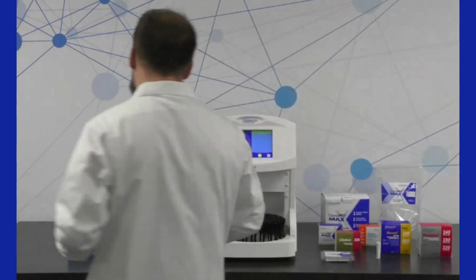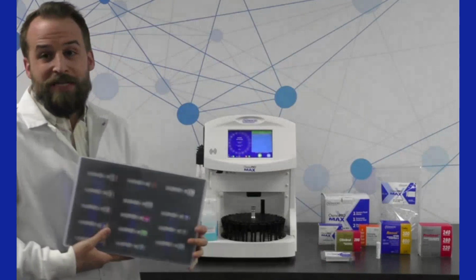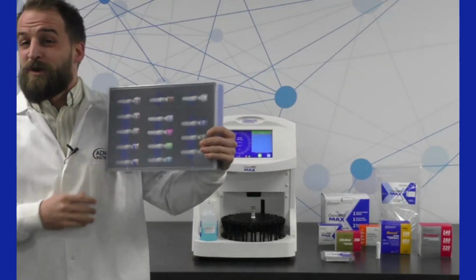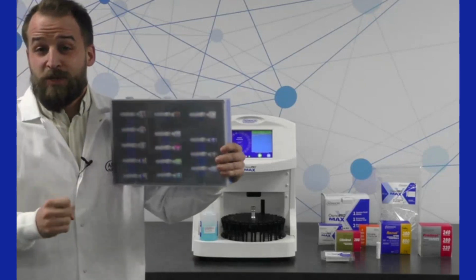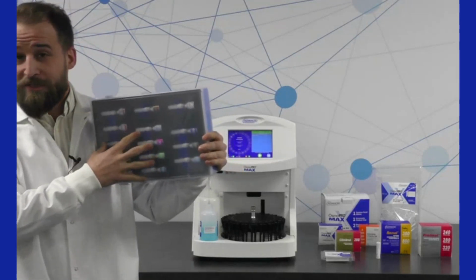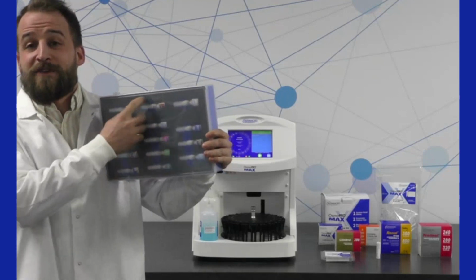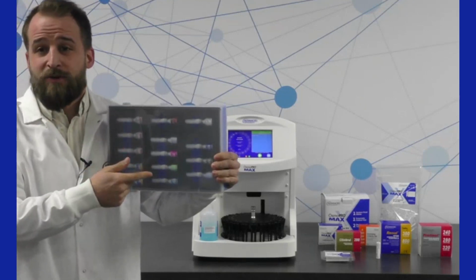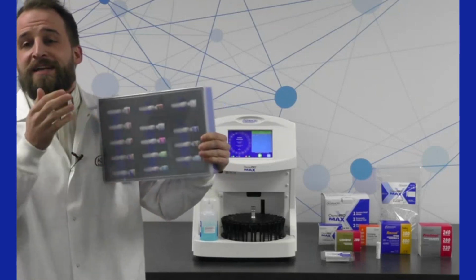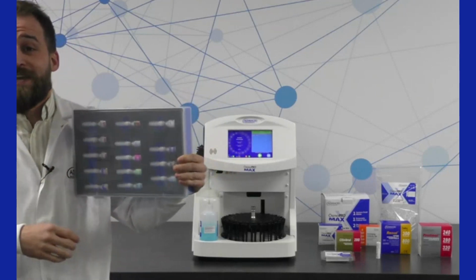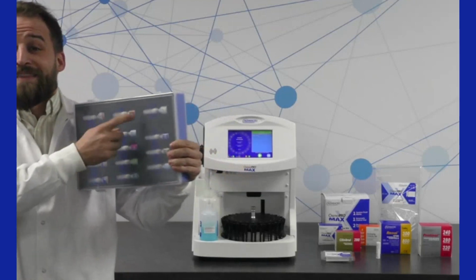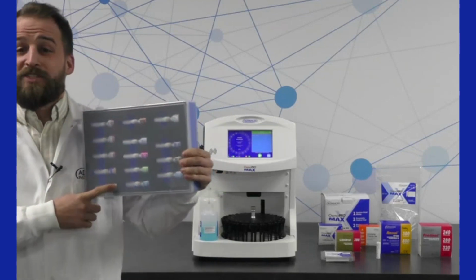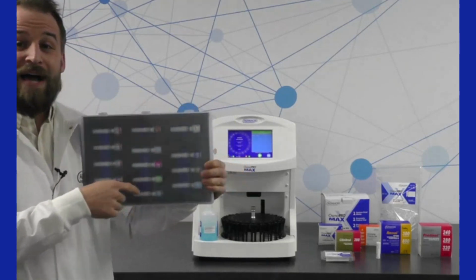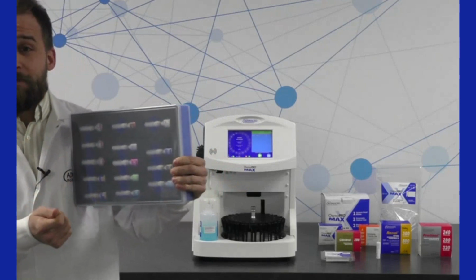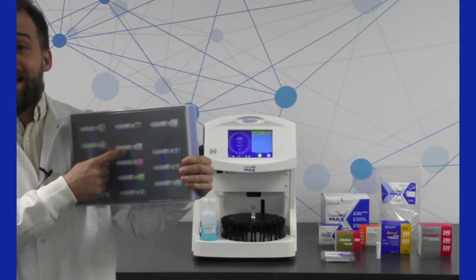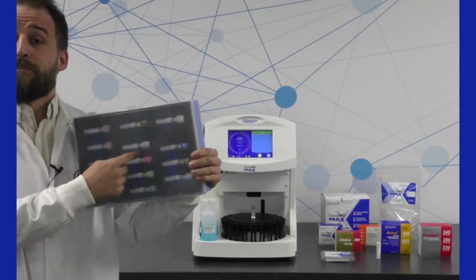One other thing I want to mention that I think is pretty cool, that just makes everything that much more easier, is this adapter set. For those of you who have used a discontinued instrument of ours called the A2O in the past, it also came with adapters. In this adapter set, there are different ampule adapters, so for your Protinol and Renal controls that I just described, as well as your Clinitrol 290, all of your calibration standards, and all of the standards from your linearity set, they have a corresponding ampule adapter, which makes it really easy for the instrument to identify what you're loading into the turntable, because every one of these has an identifier telling you which ampule to put into the adapter.